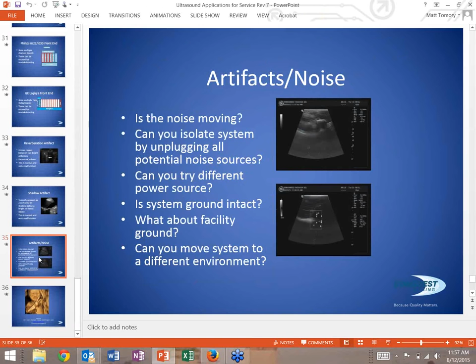Can you isolate the system by unplugging all potential noise sources? When you get this noise artifact on the screen, look at the system itself. Are there peripherals connected, like a VCR or a black and white printer? I know this is kind of old school, most systems don't have those connected these days, but a system may have an external monitor in the room, or a network cable connected. Can you isolate the system so it's just plugged into the wall with nothing else connected? And by removing those things, has the noise gone away?